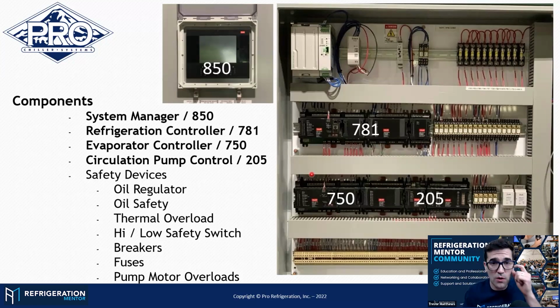This is exactly what we've been training a lot of the Pro dealers on, walking them through step by step, because one of the biggest things, it's usually not the control issue, like the programming issue. You know, that programming is done 99% of the time by the manufacturers, and maybe adjusted a little bit for a specific application. If you're up in Alaska versus down in Southern California, there might be a little bit of changes. But besides that, all the wiring is going to be on the wiring diagram. You've got to dive into that to follow while you're troubleshooting. Probably just don't be winging this stuff. You've got a nice panel there, all with the labels. Follow the label. So I love it.